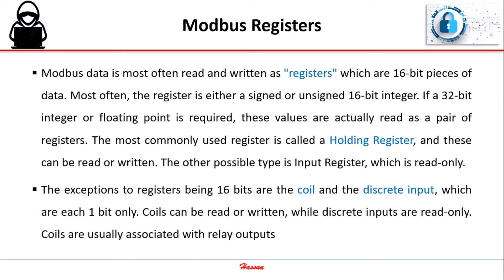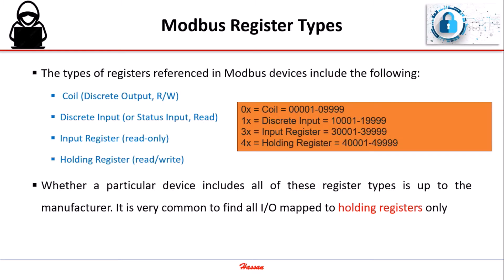Modbus data is most often read and written as registers, which are 16-bit pieces of data. The register is either a signed or unsigned 16-bit integer. If a 32-bit integer or floating point is required, these values are read as a pair of registers. The most commonly used register is called a holding register, and these can be read or written. The other possible type is the input register, which is read only. The exceptions to registers being 16-bits are the coil and the discrete input, which are each one bit only. Coils can be read or written, while discrete inputs are read only. Coils are usually associated with relay outputs. It is very common to find all I/O mapped to holding registers only.